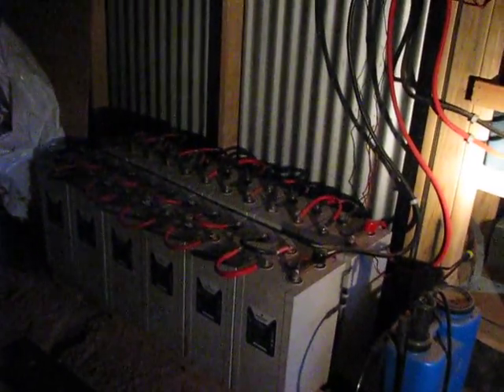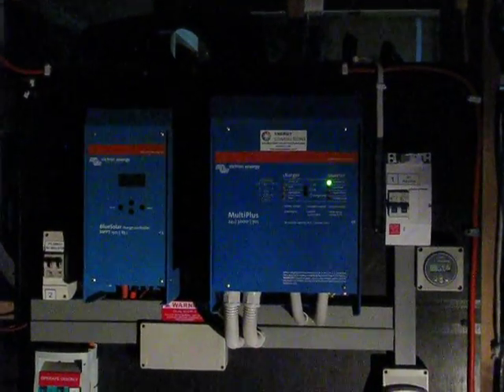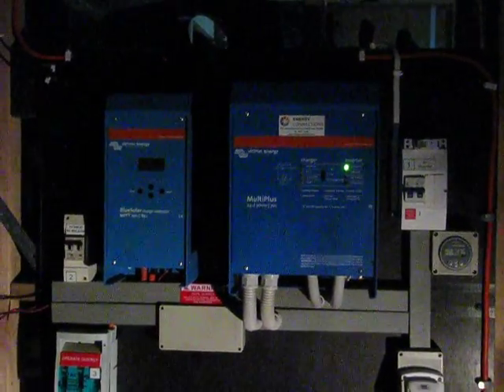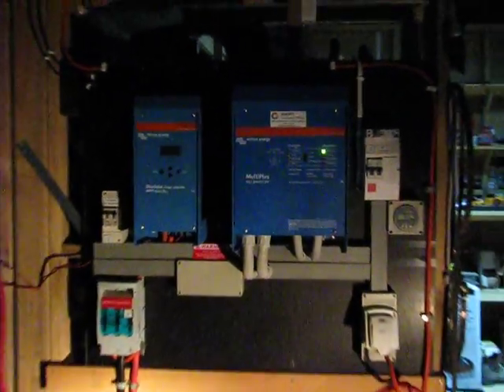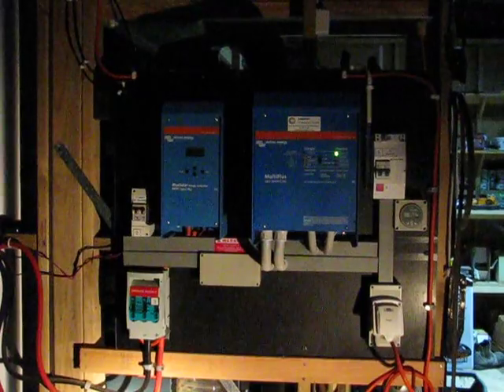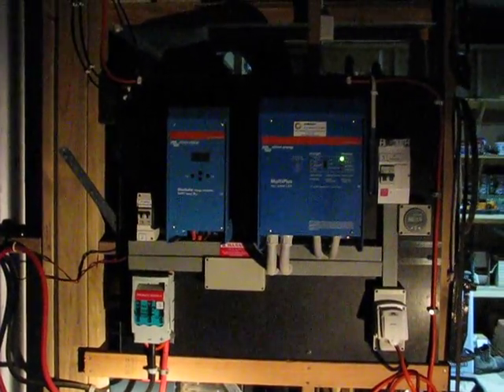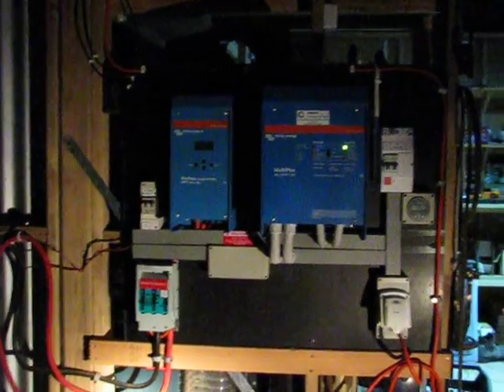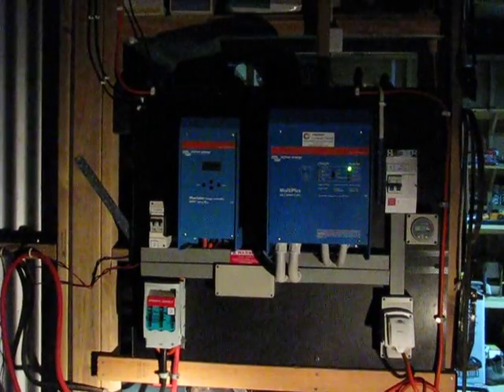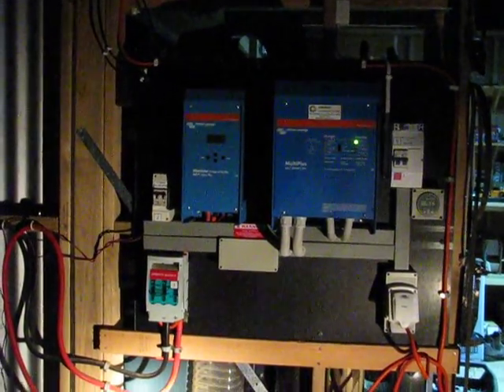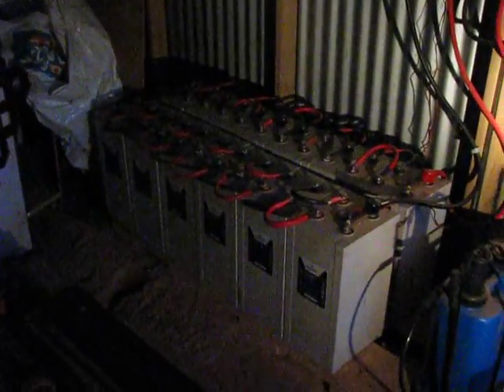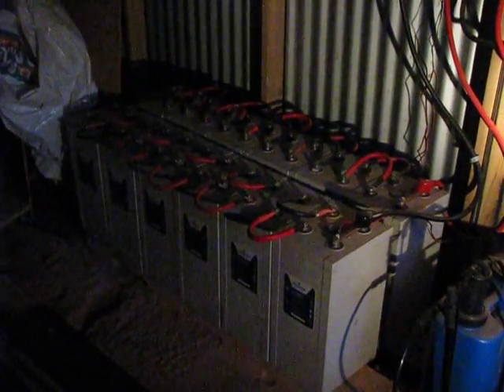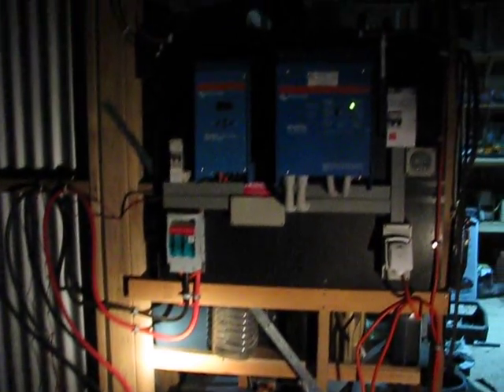It won't screw around with your electrics or blow things up. It's the best thing to power this inverter up to charge the batteries. If those batteries drop down to 50% and the equipment goes off on low voltage, you've used a cycle up. What I choose to do is a quick battery run to bring the batteries back up. It might only take an hour or two, brings them up from that 75% range to 95%. It might cost you five bucks but it saves that million dollar battery bank from going under volt or down to a level considered full discharge.